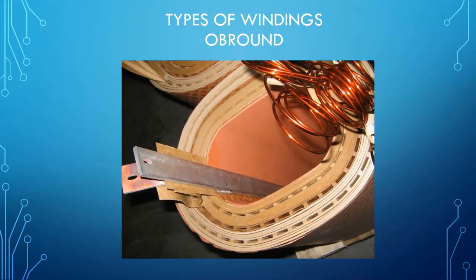Here's a nice picture of an ob-round winding. And as you can see, it has some of the properties of a rectangular and some of a circular. It is easier to manufacture because the core steel, much of it can be cut to the same length, but you have some advantages with regards to the short circuit strength. During a short circuit, every transformer tries to go round, okay? And transformers that fail during a short circuit always fail at the corners. So that is why many customers prefer ob-round or circular windings.